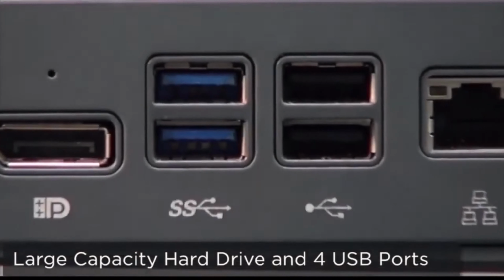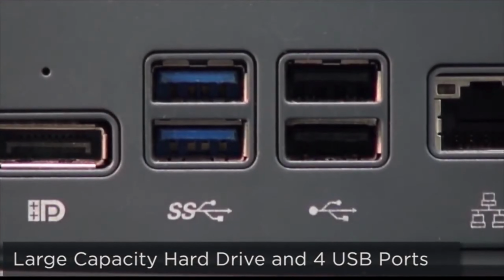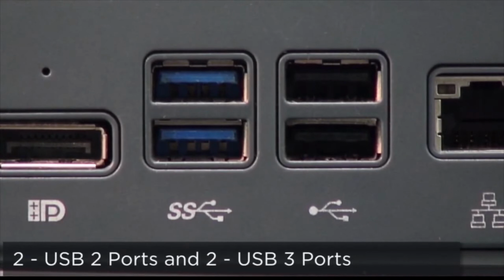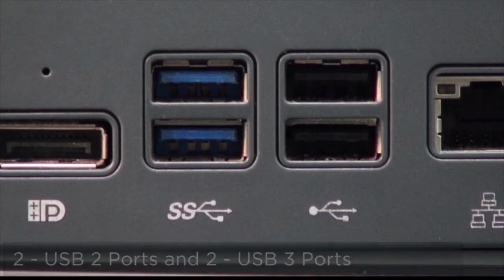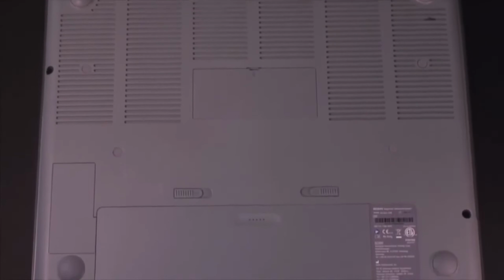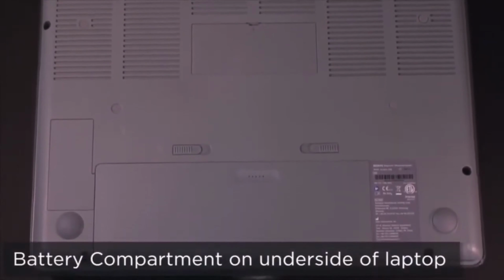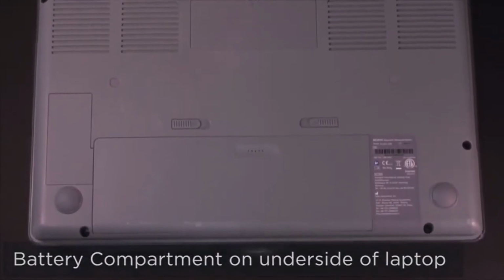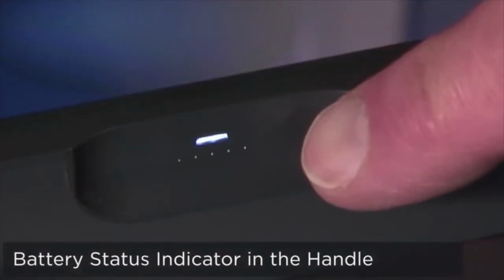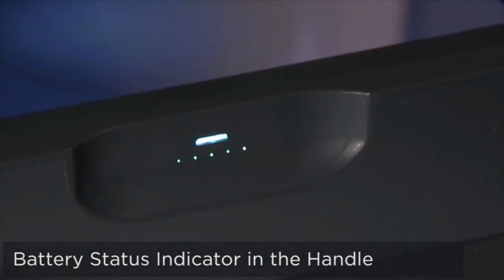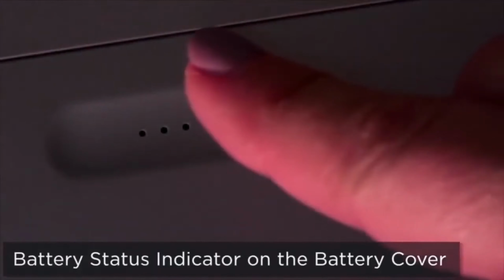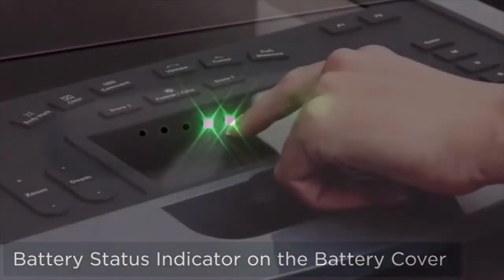The Acclarix AX8 features a large capacity hard drive and four USB ports, two USB 2 and two USB 3, to facilitate archiving of images and transfer for permanent storage. Additionally, the AX8 features battery operation of approximately 60 minutes normal use, allowing you to move easily from room to room for maximum efficiency. There are two touchscreen sensor battery level indicators, one of which is conveniently located in the handle and the other on the battery cover.